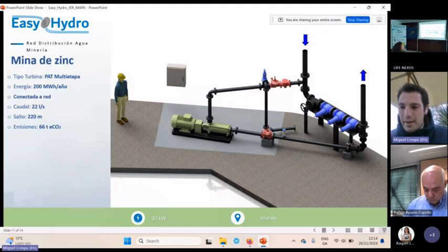The conditions at the inlet of the pressure reducing station were 27 bars. At the outlet, we had 5 bars, and what we proposed was this bypass system, to take advantage of the 22 bar to be transformed into electricity. With a flow rate between 15 and 22 liters per second, and a net head of 220 meters, we were producing about 30 kilowatts.